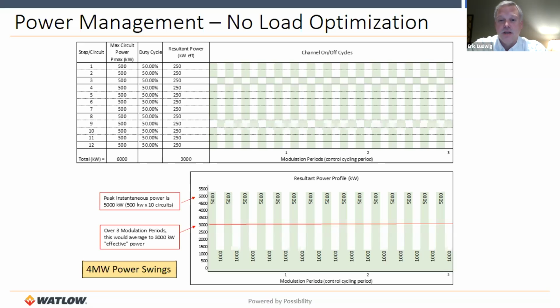Now effectively that averages out to 3 megawatts of power delivered into your overall system. So your system is still seeing the 3 megawatts it might need at that 50% duty cycle, but your feeder system is swinging by 4 megawatts within that, and that can be very detrimental to your feeder systems.